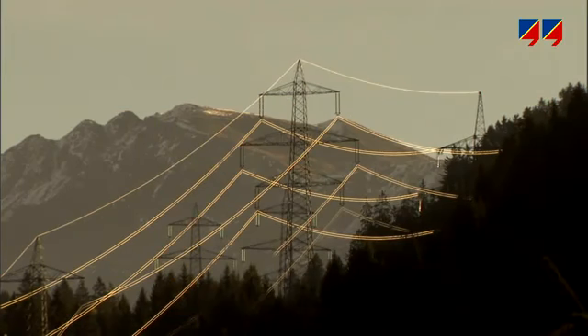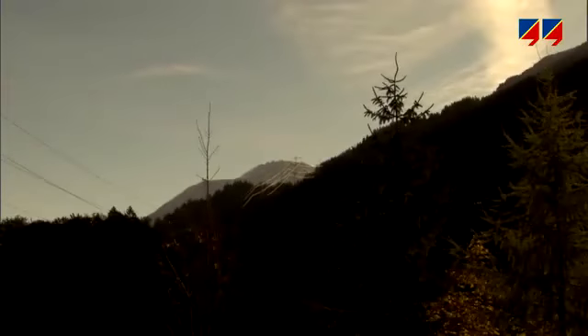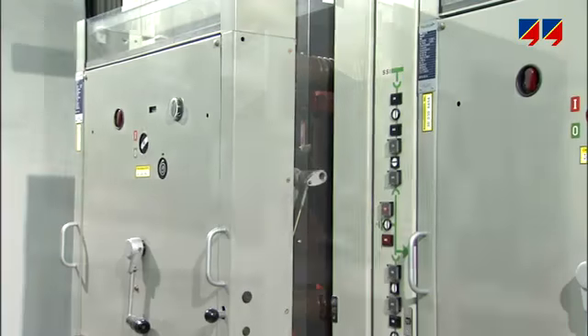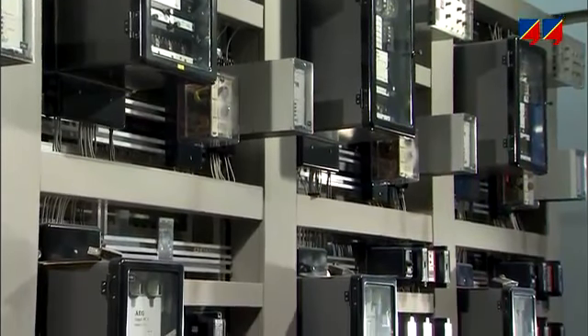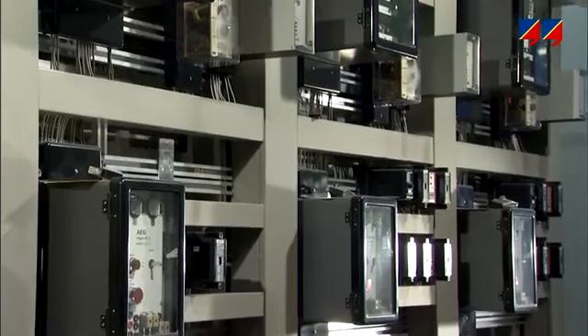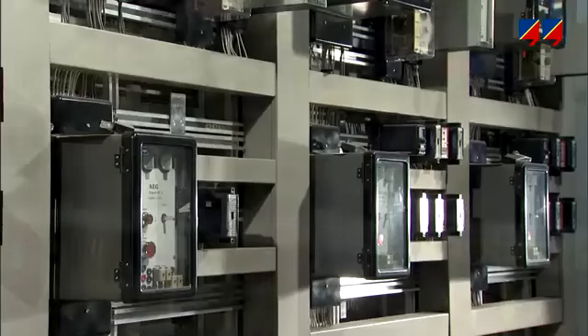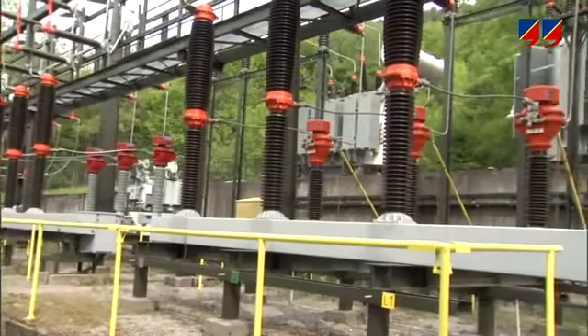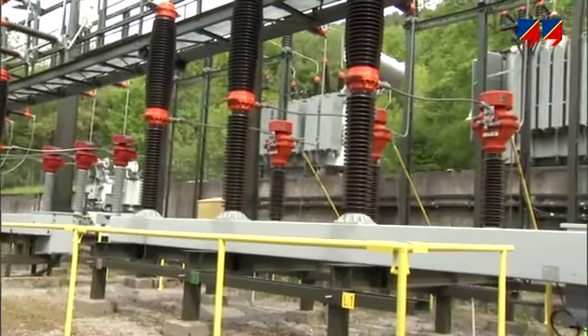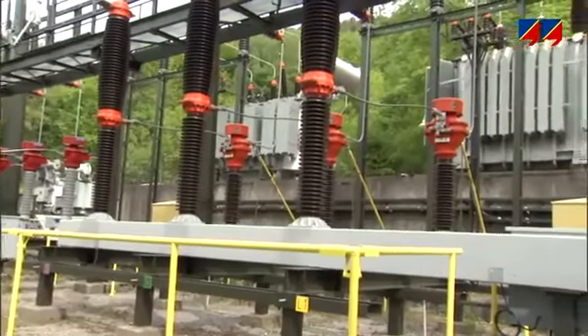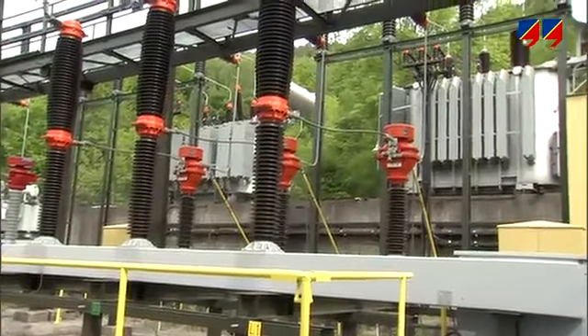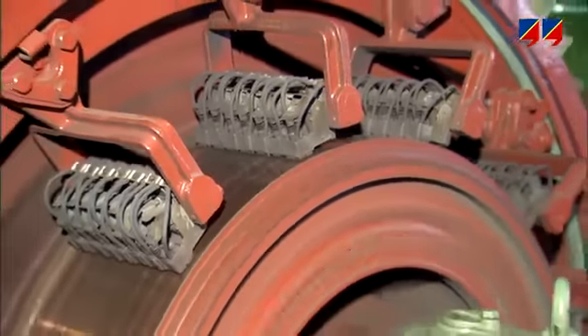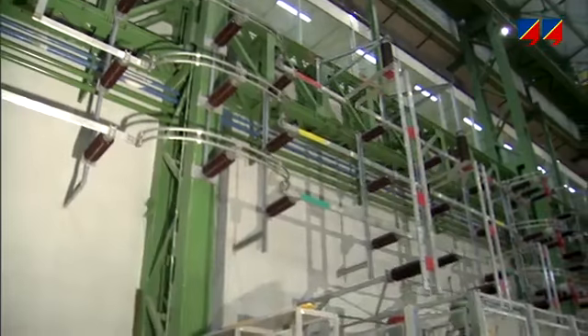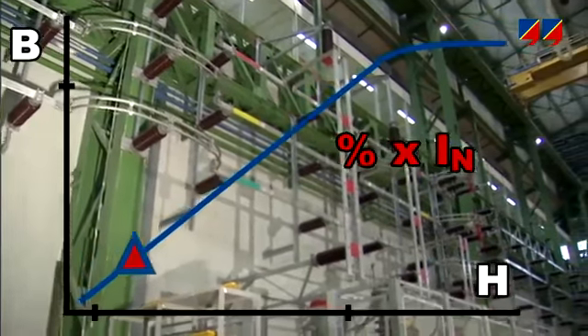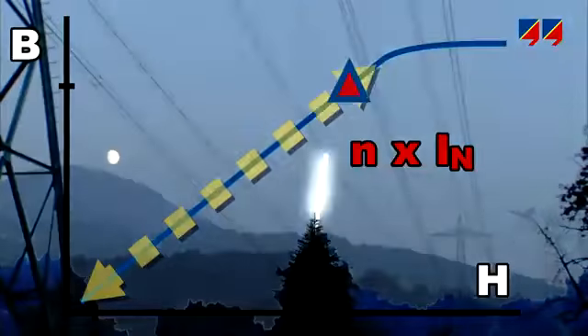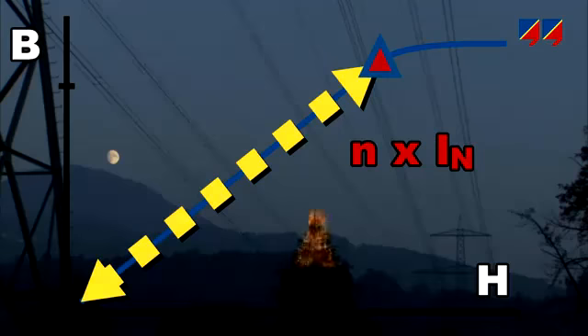The goal of each protection system is safe and selective tripping. Relays are connected to the CT's secondary side and can only make correct trip or no trip decisions if their input current is correct. Ensuring this is the task of protection CTs, which must be able to transform currents flowing in generators, transformers, or bus bars, ranging from a few percent of rated current up to many times its value for short-circuit faults.